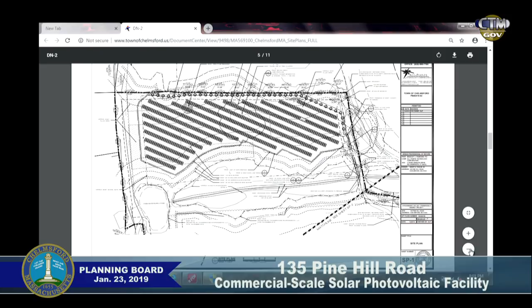The posts and panels themselves are a ground mount system. It's post driven, so you've got basically an I-beam that's just driven into the ground with a pile driver, and then from there a racking system is installed. The arrays are supported on the racking system. Wiring for those is run basically to the end of each of the rows, and then we have underground conduit from the inverters that run back to the switchgear pad at the beginning of the site.